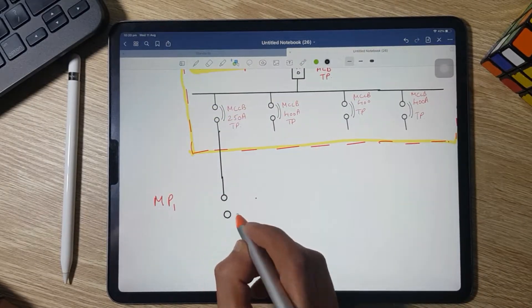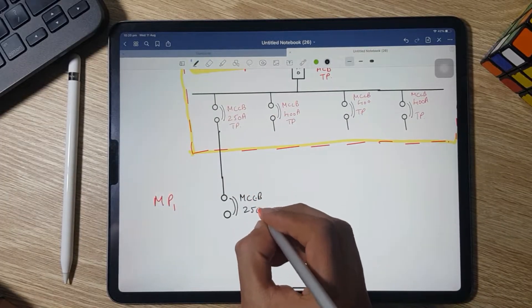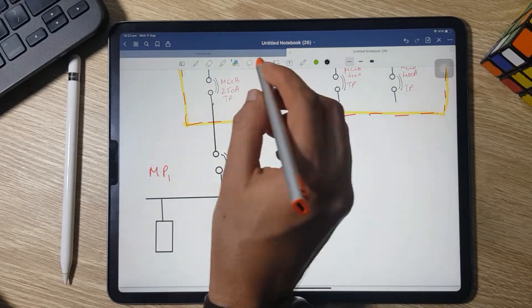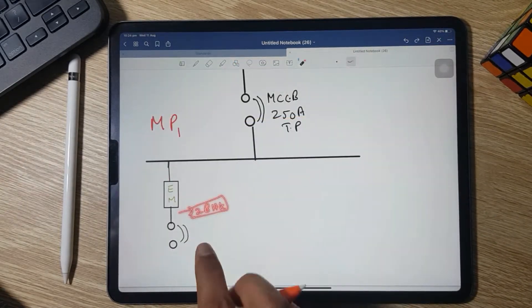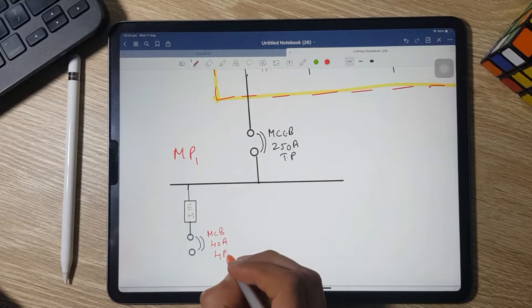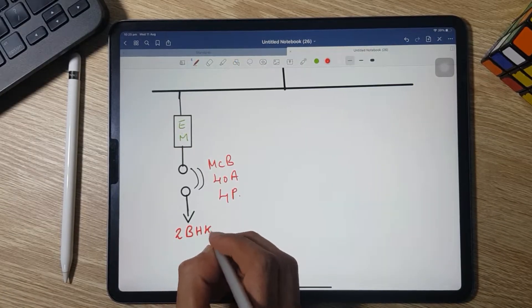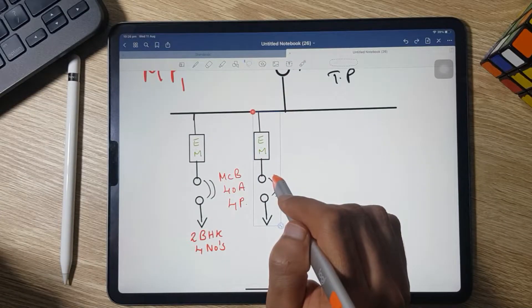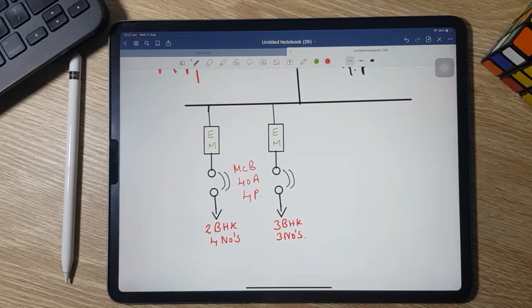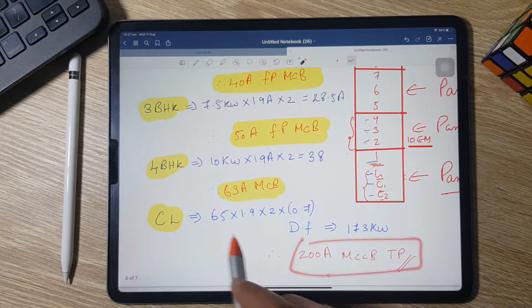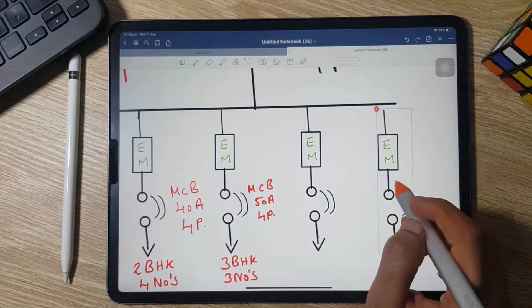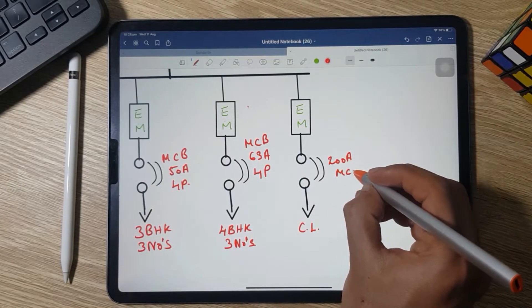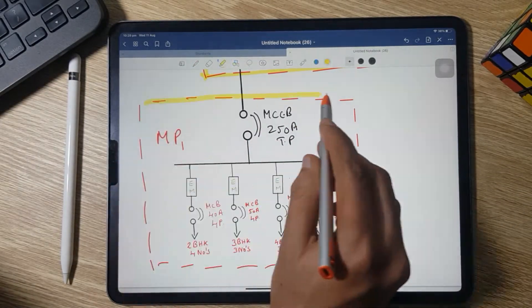Drawing the layout for Meter Panel 1: the main MCCB is 250 A triple pole. Inside, the energy meters are arranged by flat type. For 2 BHK (4 numbers): 40 A four-pole MCB with 5 kW energy meter. For 3 BHK (3 numbers): 50 A four-pole MCB with 7.5 kW energy meter. For 4 BHK (3 numbers): 63 A four-pole MCB. For common load: 200 A triple-pole MCCB.